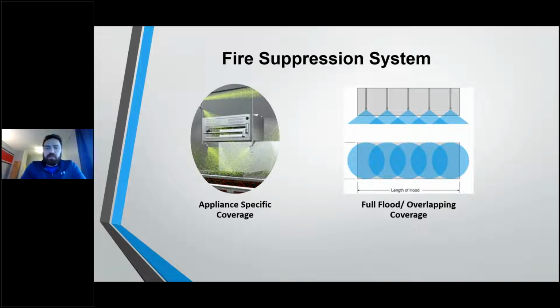The other type of fire system that you're going to see in the market is a full flood or an overlapping coverage system. These systems, in a lot of instances, will also have a water-based component to them. So they'll have some sort of effluent dump, and then they'll have a continuous water supply coming on in order to douse the fire. These full flood systems are commonly used in test kitchens where you're going to be changing out a lot of different appliances. So some major manufacturers or major retail chains that are going to have their own brand of food are going to have test kitchens associated with them, so they can test the nutrients of their food. They can test how to cook these foods in different appliances. So those types of operations are commonly switching their appliances out because they're switching what they're testing. So that's where a full flood system is going to come into effect.